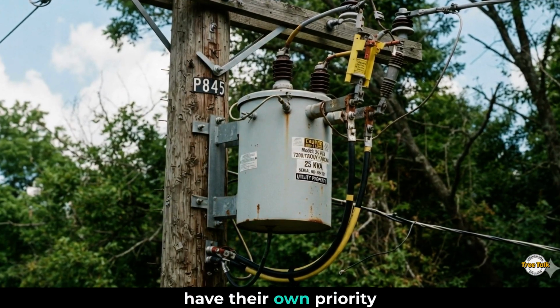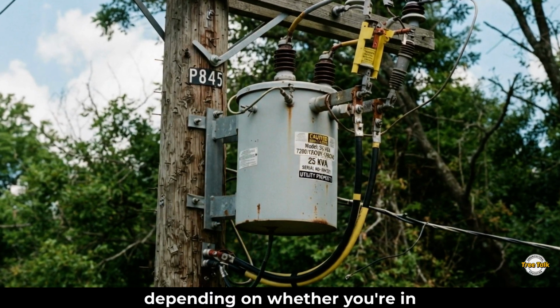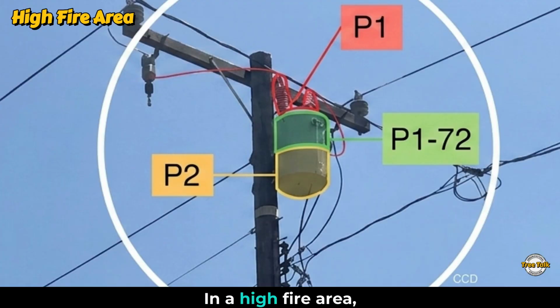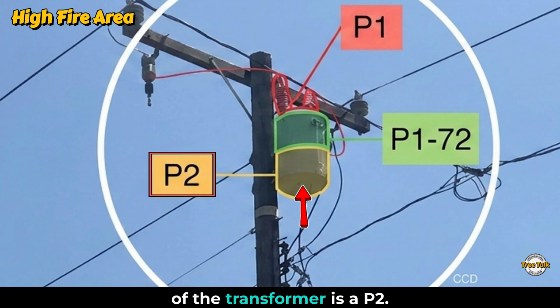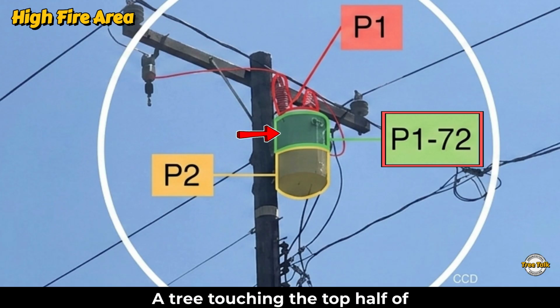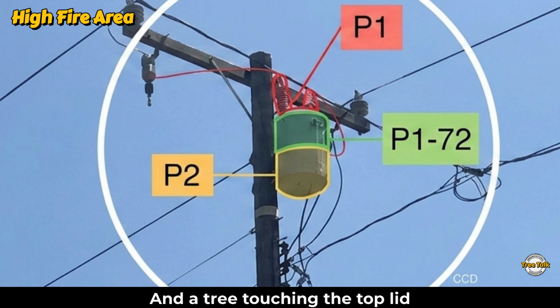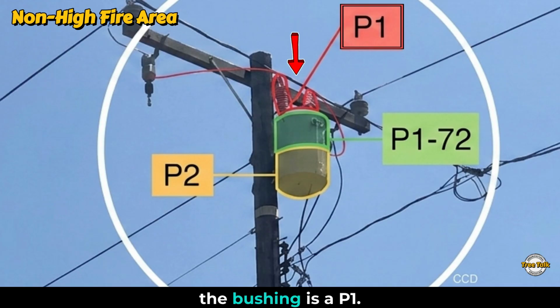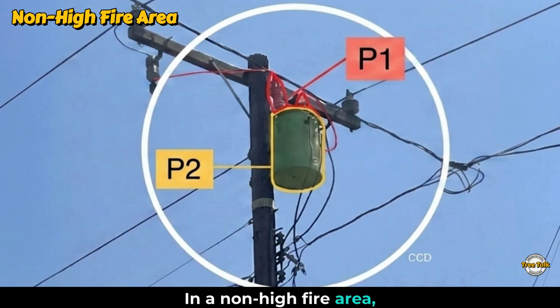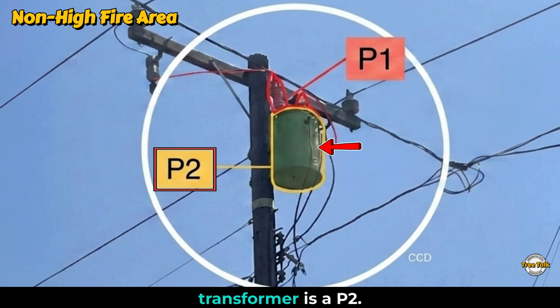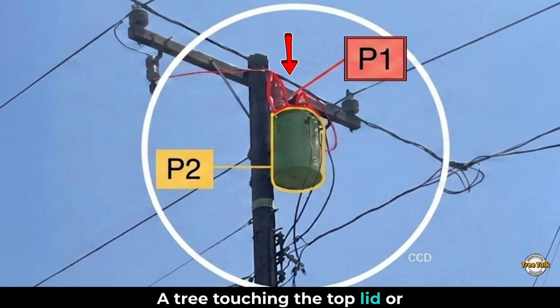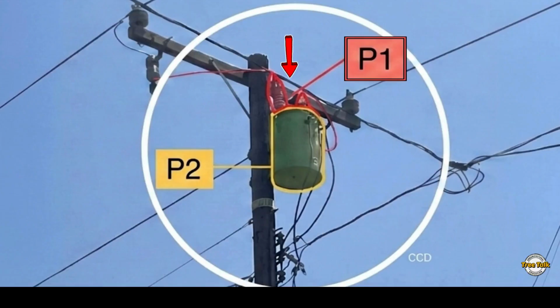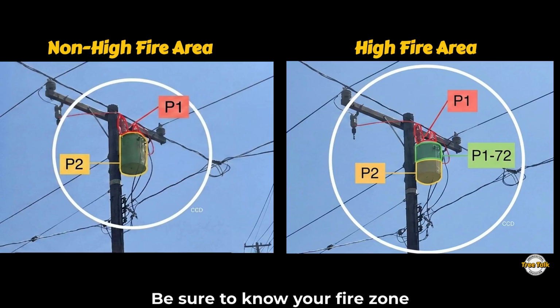Transformers specifically have their own priority classification, and it splits differently depending on whether you're in a high fire area or not. In a high fire area, a tree touching the bottom half of the transformer is a P2. A tree touching the top half of the transformer is a P1-72. And a tree touching the top lid of the transformer, or the bushing, is a P1. In a non-high fire area, a tree touching anywhere on the sides or the bottom of the transformer is a P2. A tree touching the top lid or the bushing of the transformer is a P1. So the dividing line moves depending on the area. Be sure to know your fire zone for your circuit when you're checking transformers. And if vegetation is touching, know exactly where the contact is: bottom half, top half, or the top lid or bushings.